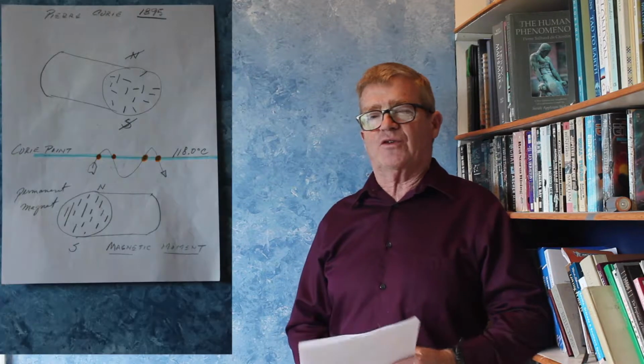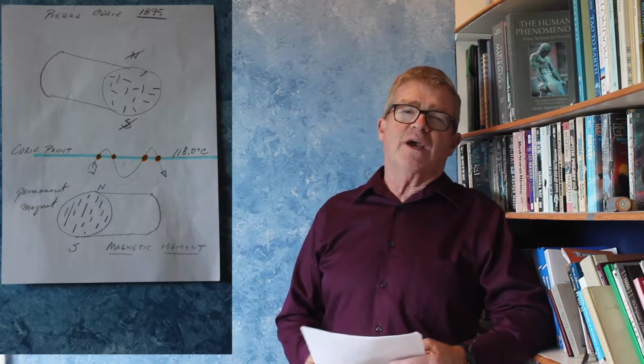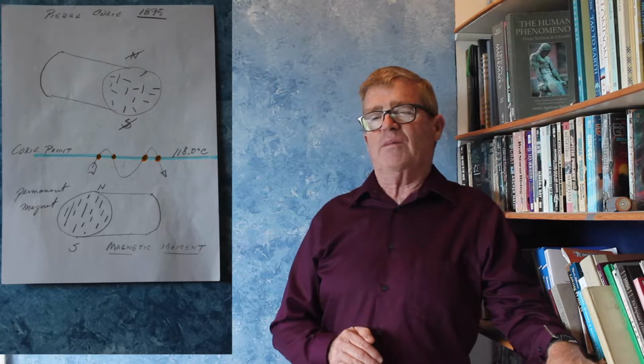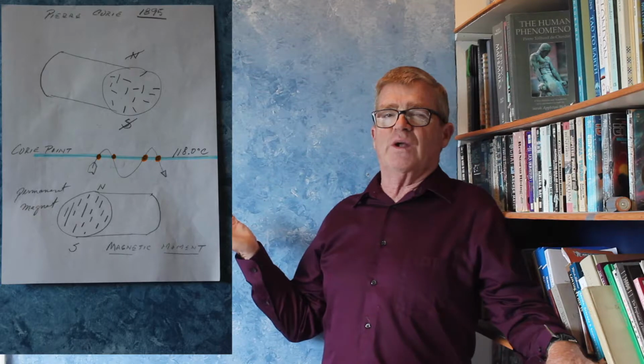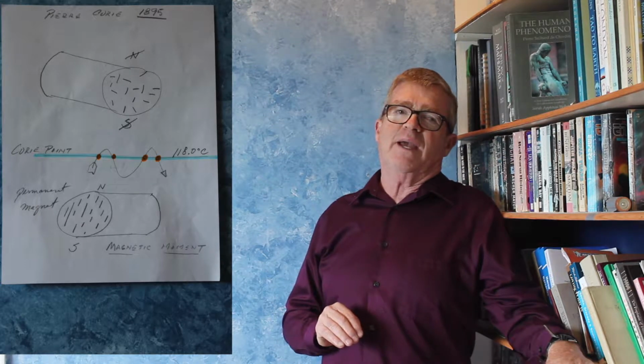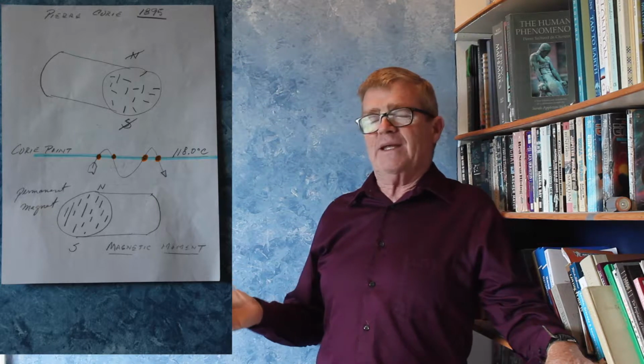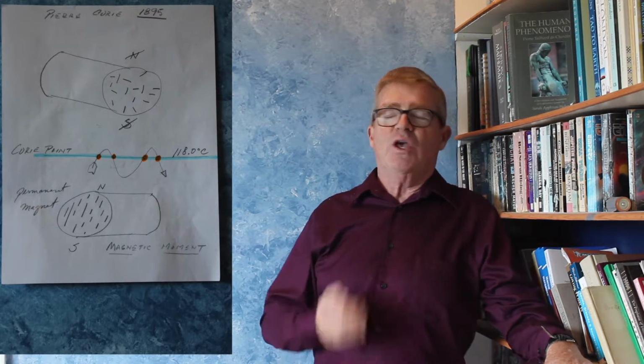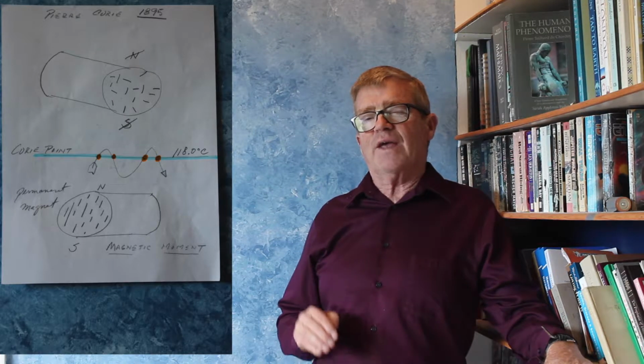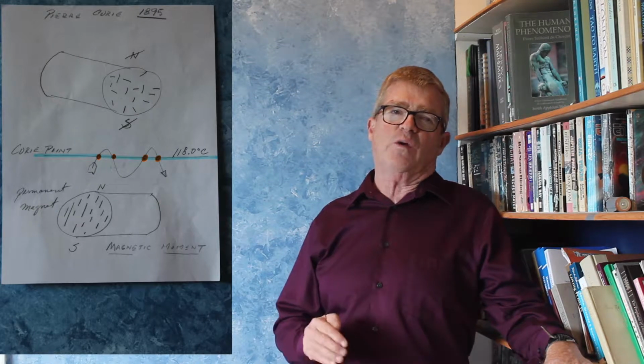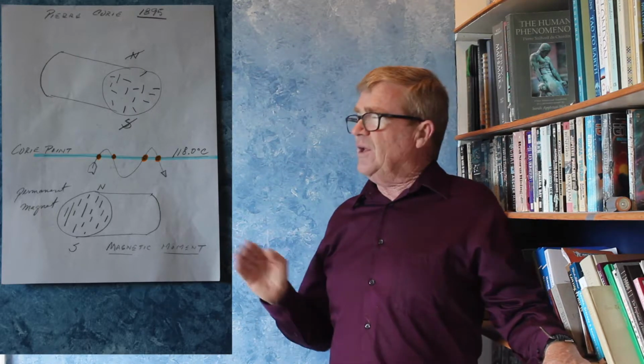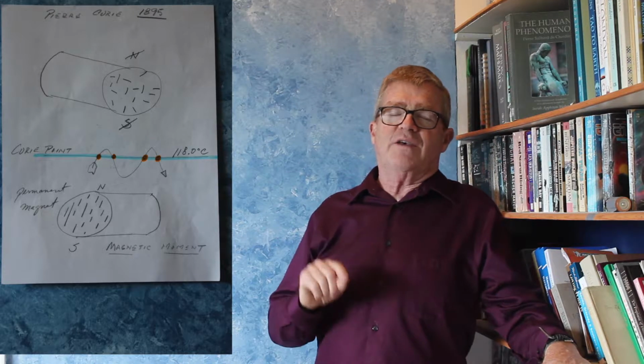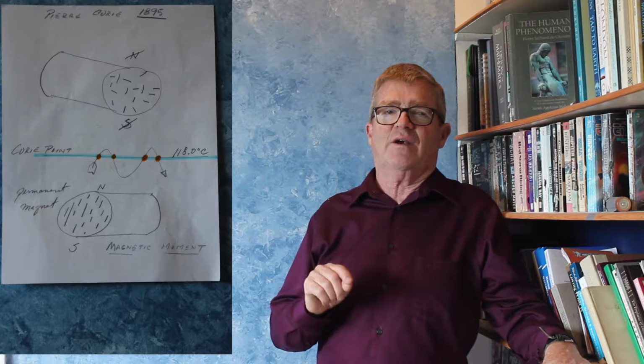So how does the switch work and why is it traceable? 120 years ago, Pierre Curie discovered there was something really cool about permanent magnets. He found that if you raise the temperature of one above a critical value, it stopped acting like a magnet. Its ability to act like a permanent magnet resumed the minute you went below that temperature. In modern terms, we'd say the magnetic moment of all the atoms was aligned below the critical point and got all discombobulated above it. Now you can see from my drawing that this particular device trips at 118.0 degrees centigrade. And the fact that it's reproducible and precise allows us to tie a temperature standard to it, which links us all the way to the SI.